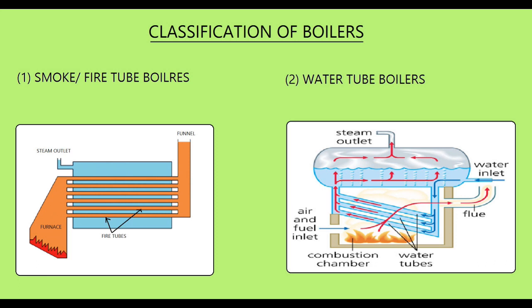Smoke or fire tube boilers: combustion gases pass through tubes which are surrounded by water. Because of the production of low saturated steam, these boilers are normally used for auxiliary purposes on board, like heating. Water tube boilers: water contained in small bore tubes is exposed to the heat of combustion. Compared to fire tube boilers, generation of steam is at much higher pressures and temperatures, and the steam rising process is much quicker.